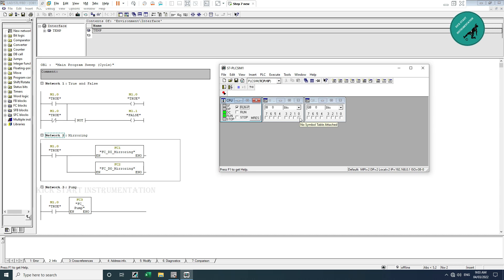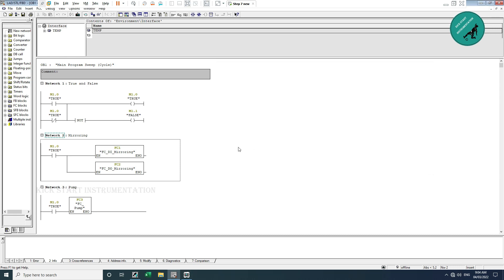When I0.0 is activated, Q0.0 is activated — I did not write the logic here in the main OB1, it is in FC Pump which is FC3. Even if I make I0.0 false, the output still remains active due to latching. When I make the stop true, the output goes false. The same logic as before, but now split into separate functions so the main OB1 remains as simple as possible. Let me stop the PLC.